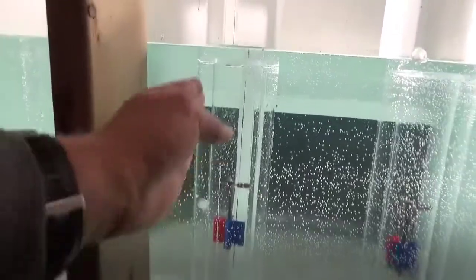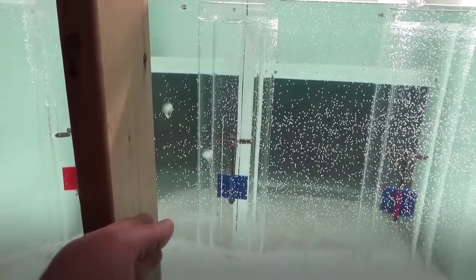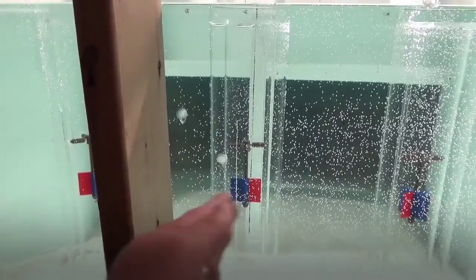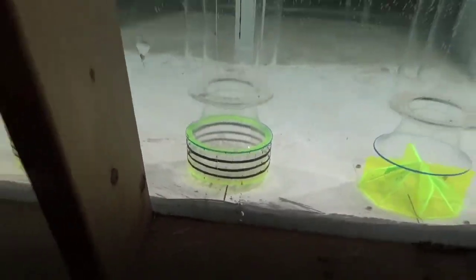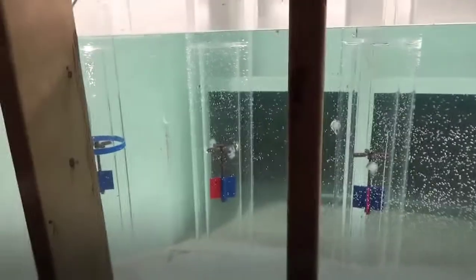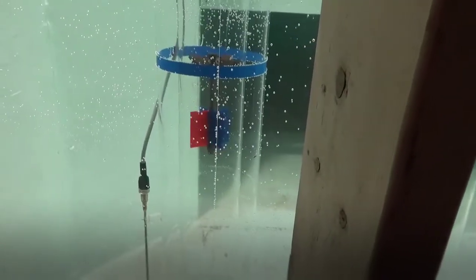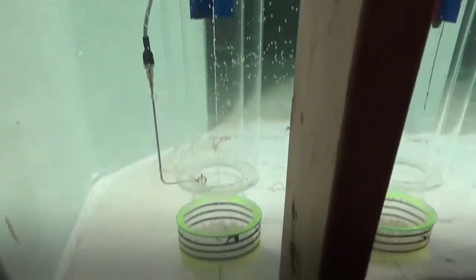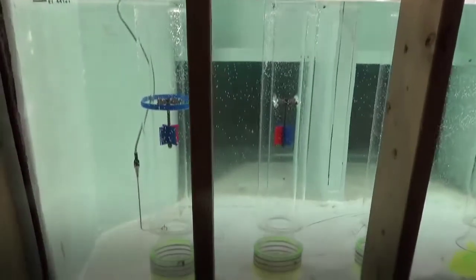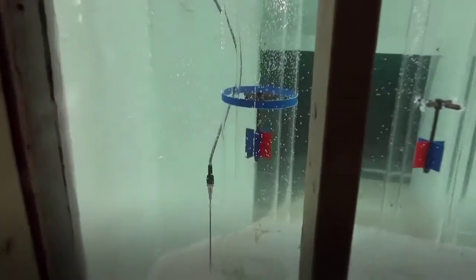Pump 1 is in line with that wall, so its pre-swirl has never been really high, but there may be a bit of oscillation. That's eliminated with the basket. So through the whole range we see the issue, and through the range it's all corrected. We're going to flip over this pump right here and turn on this one right now and show you that the basket works. Okay, so this pump's running, very high pre-swirl, and this outer pump's running, and it's just no pre-swirl at all, very, very low. So you can see they're symmetrical on the 2 sides. In the baseline video you saw they look identical, just different directions. The basket's very effective over this whole range of flow rates.